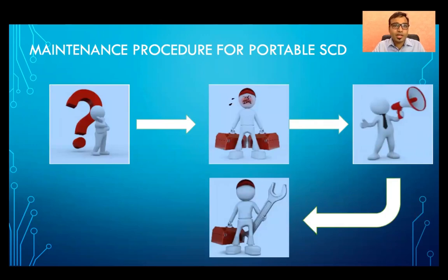To appreciate the advantage of the automatic earthing and short circuit device, let's quickly discuss the maintenance procedure which needs to be followed in the case of a portable short circuit device. In case of any preventive maintenance or breakdown maintenance, after obtaining the permit to work, staff has to find out where the portable short circuit device is kept. Then they have to carry this bulky device to the place where the maintenance is to be done, which is typically 700 to 800 meters away from the station.